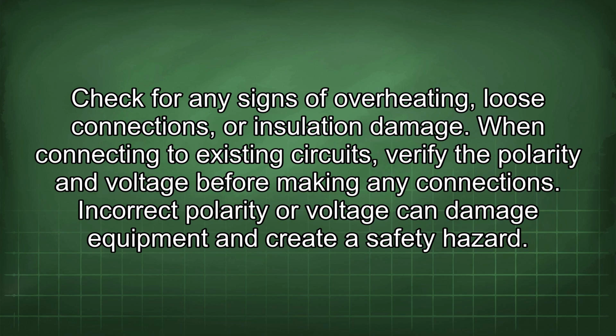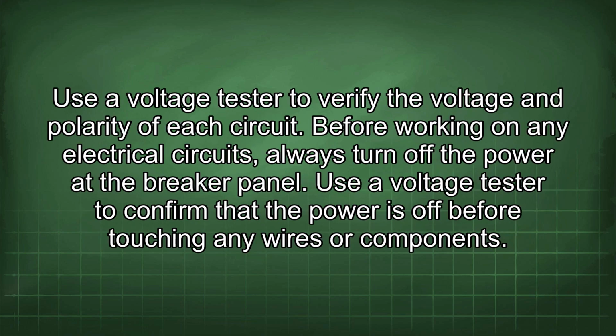When connecting to existing circuits, verify the polarity and voltage before making any connections. Incorrect polarity or voltage can damage equipment and create a safety hazard. Use a voltage tester to verify the voltage and polarity of each circuit. Before working on any electrical circuits, always turn off the power at the breaker panel. Use a voltage tester to confirm that the power is off before touching any wires or components.